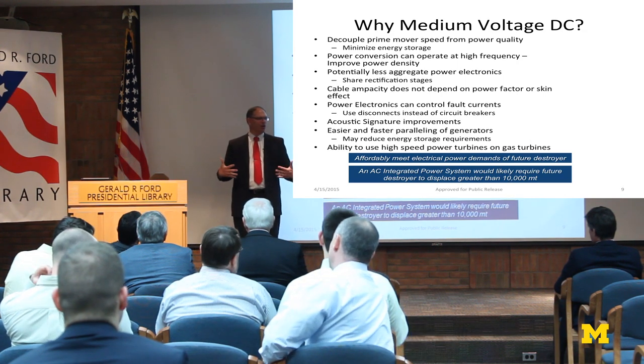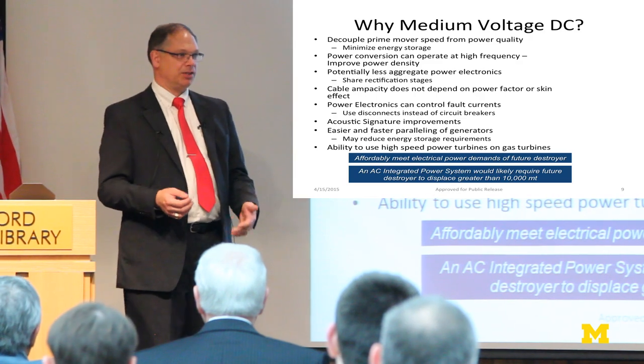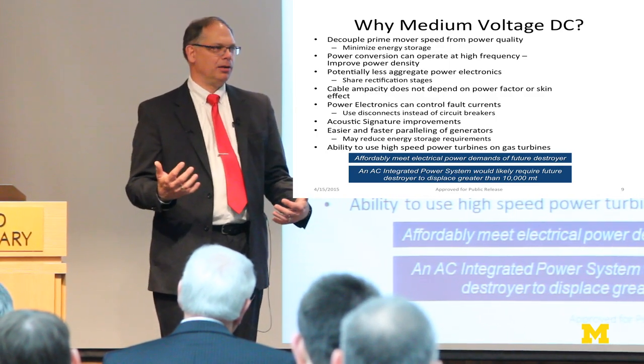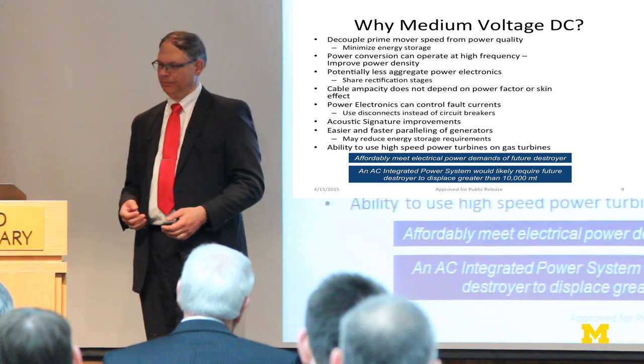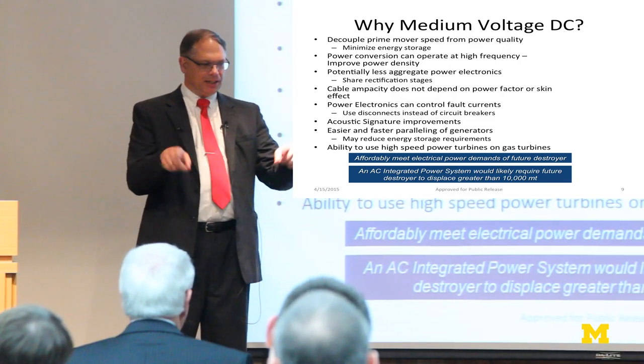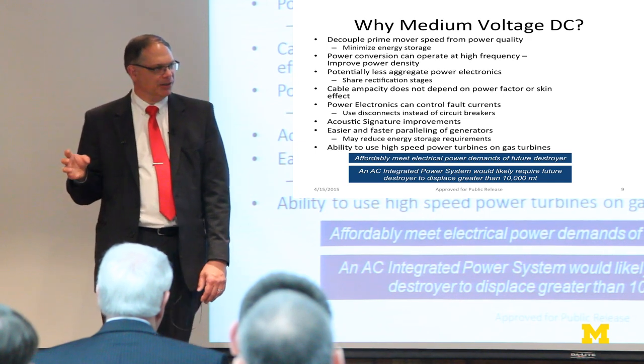The whole challenge area of pulse loads disappears. Now the only thing I have to match is voltage — the harder part of trying to keep machines in time synchronism is gone. I can take advantage of that by using energy storage. Because I'm not keeping them in synchronism, I can actually allow the generators to slow down — use the stored rotational energy in the generator as a flywheel. I may even want to put more mass on it to turn it into a flywheel, rethinking how I build these machines and where I want the energy storage.